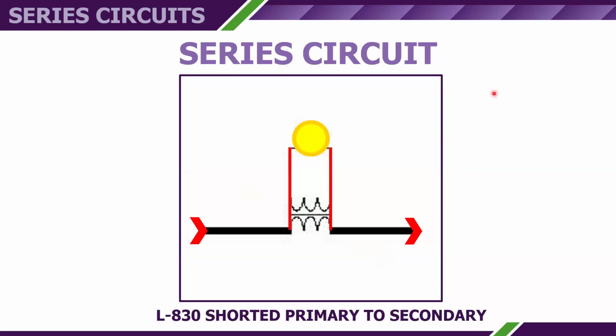And what I'm talking about with a primary to secondary short, here you see that you've got your primary circuit, you've got your lamp, you've got your isolation transformer. The isolation transformer is nothing more than a current transformer. It takes 6.6 amps going through the primary and converts it to 6.6 amps in the secondary. If you have a primary to secondary short, it means this line voltage that you get on the output of the regulator could be available right here on this lamp.